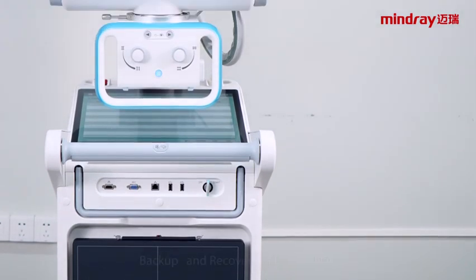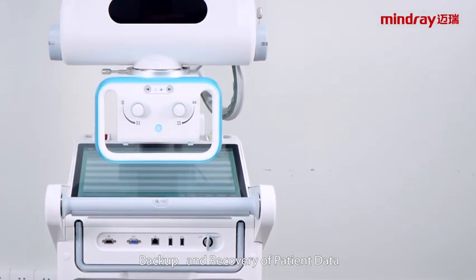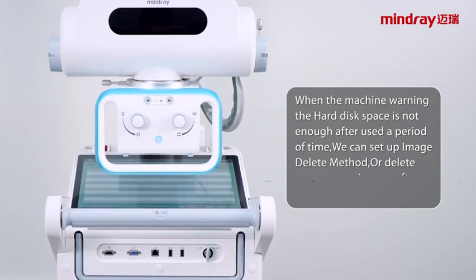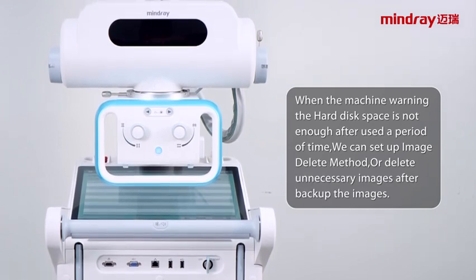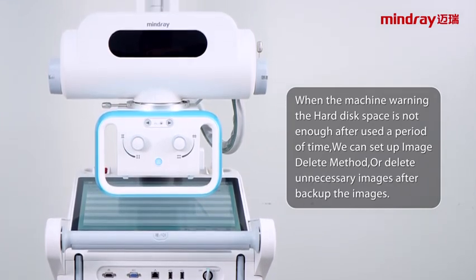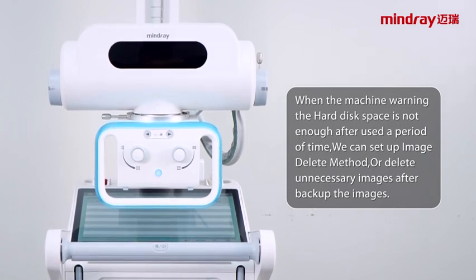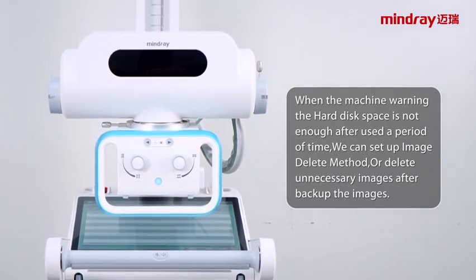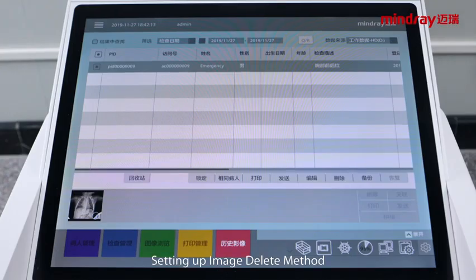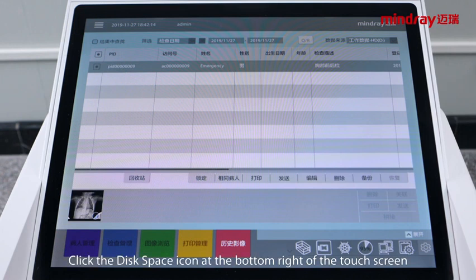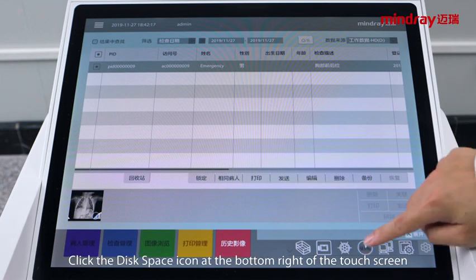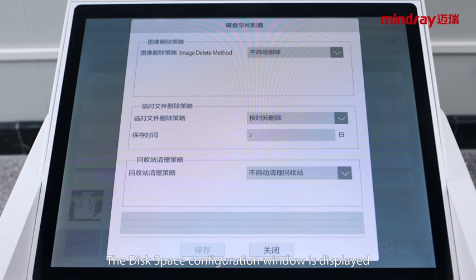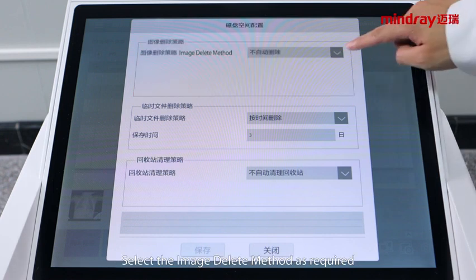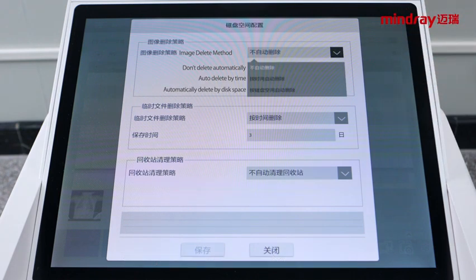Automatic delete, backup, and recovery of patient data. When the machine warns that the hard disk space is not enough after being used for a period of time, we can set up an image delete method, or delete unnecessary images after backing up the images. Setting up the image delete method. Click the disk space icon at the bottom right of the touch screen. The disk space configuration window is displayed. Select the required image delete method.